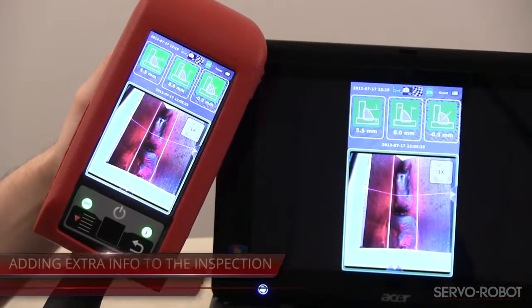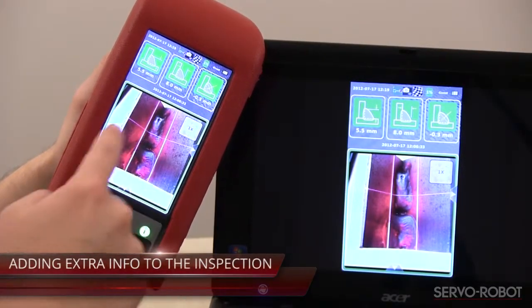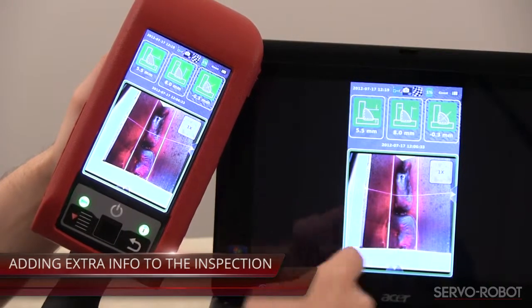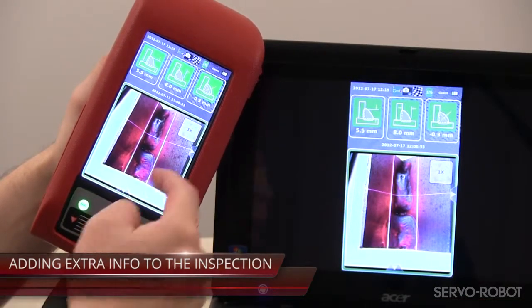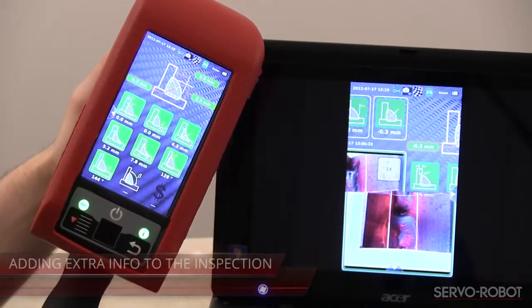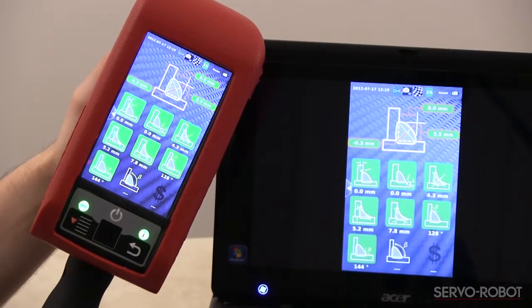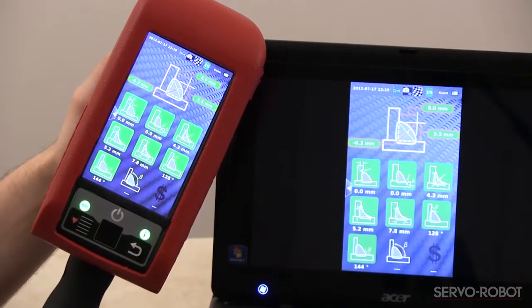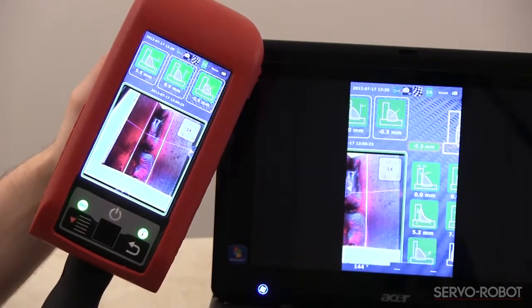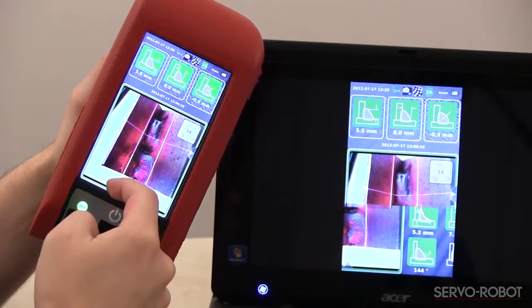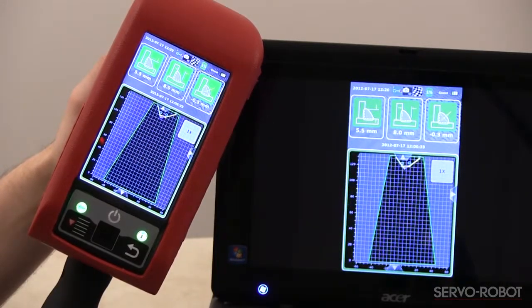The results can be seen on the remote control if the WikiScan is configured for remote display via the Wi-Fi interface. The user can then review the measurement results by swiping his finger across the screen. A leftward swipe will show the global measurement screen, while upward swipes will show the profile, and then the zoomed profile.